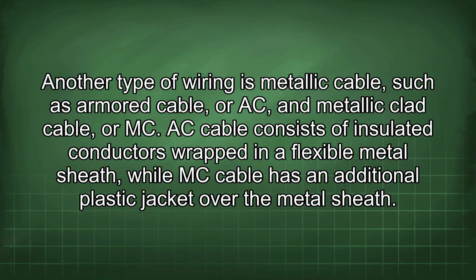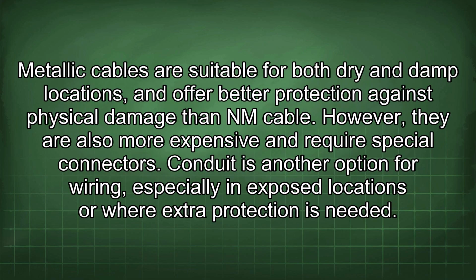Another type of wiring is metallic cable, such as armored cable, or AC, and metallic clad cable, or MC. AC cable consists of insulated conductors wrapped in a flexible metal sheath, while MC cable has an additional plastic jacket over the metal sheath. Metallic cables are suitable for both dry and damp locations and offer better protection against physical damage than NM cable. However, they are also more expensive and require special connectors.